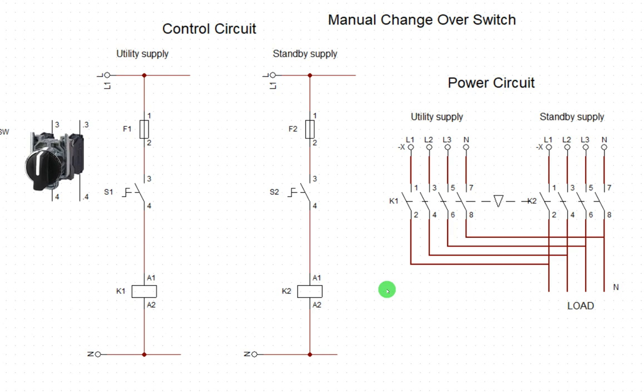Now what you are going to do is this: I'm going to simulate it so that you see how the power will jump together. This is a different power source with a different potential. This is another power source with another potential. Both of them cannot jump because they are linked here. If this one closes and this one closes, this place will get damaged because two different potentials meet together. There will be power jump and it will explode.